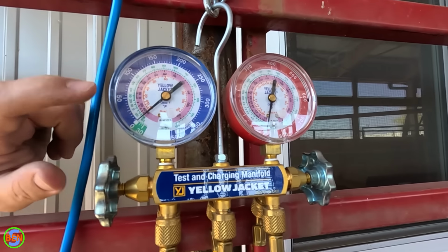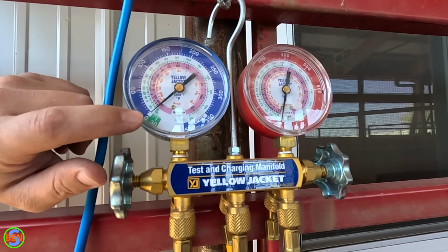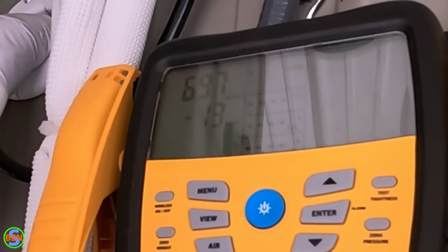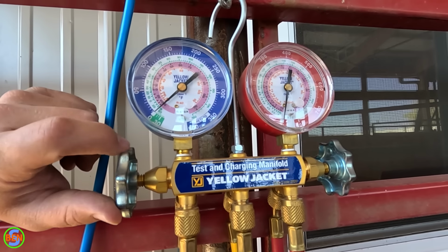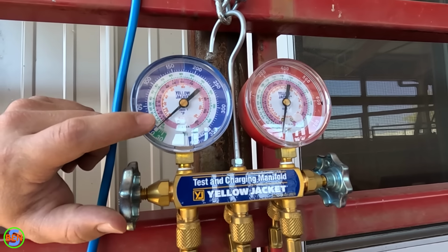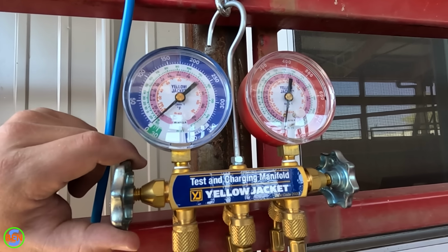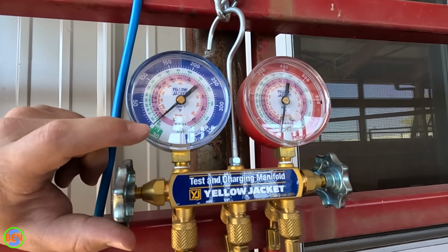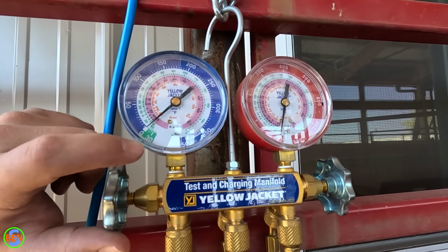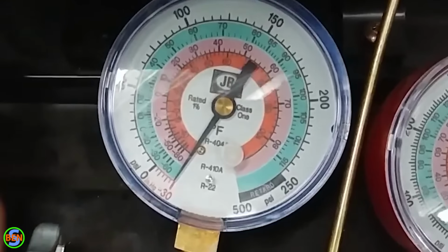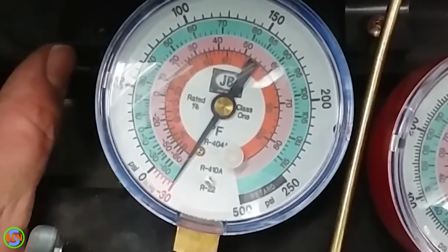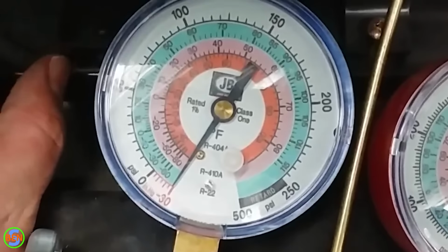And with a digital gauge, it'll actually tell you the exact amount of vacuum that you are in, which hopefully is going to be less than 500 microns. You'll then want to make sure that that vacuum holds for probably at least 15 minutes, but if you have an analog gauge, I would recommend much longer than that. I'd probably say more like an hour to 3 hours would probably be better, because it's a lot harder to see if anything is happening on an analog gauge than it is on a digital gauge.